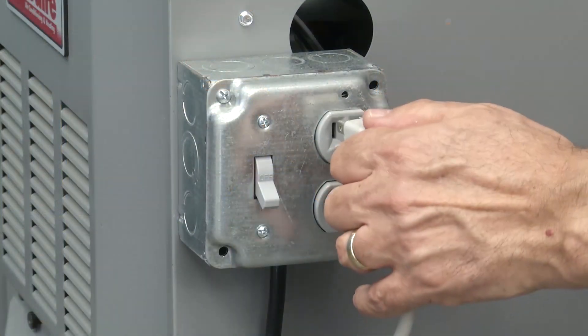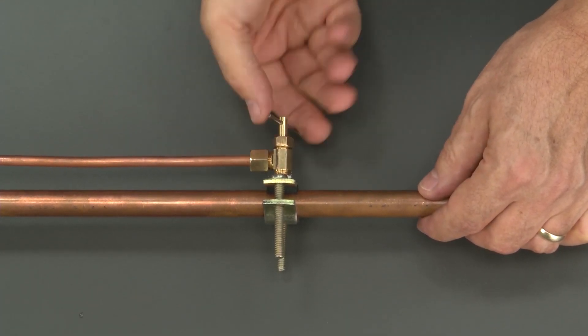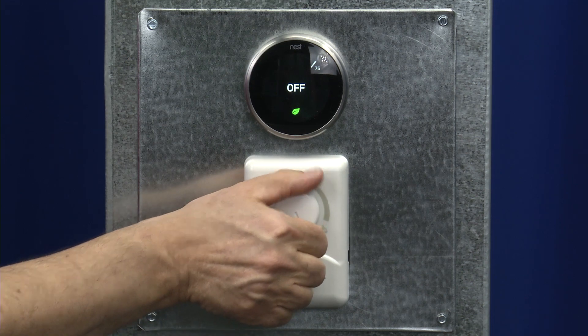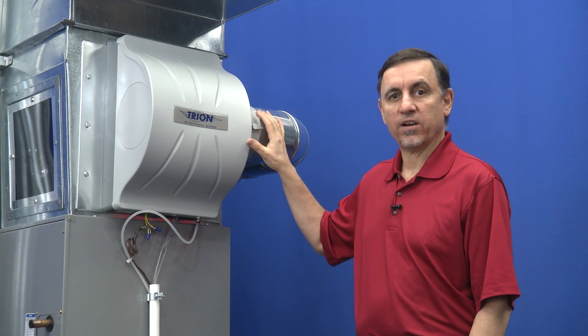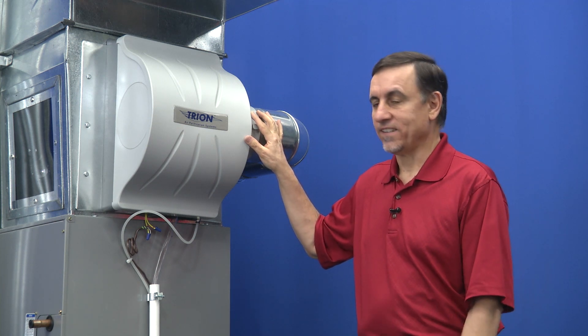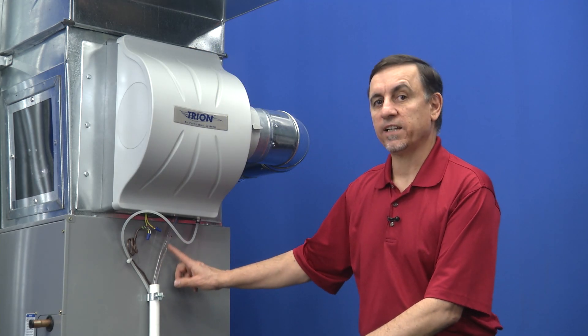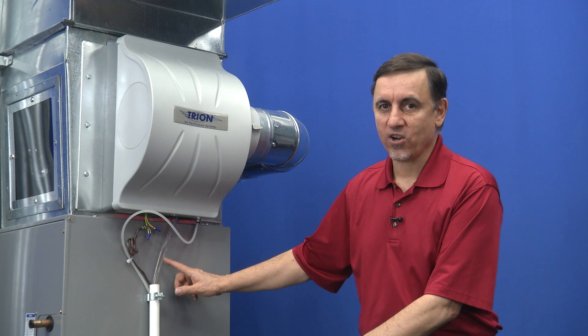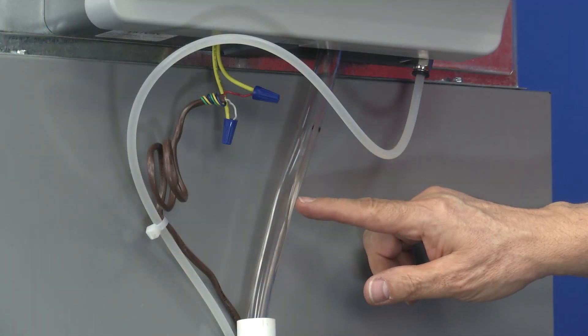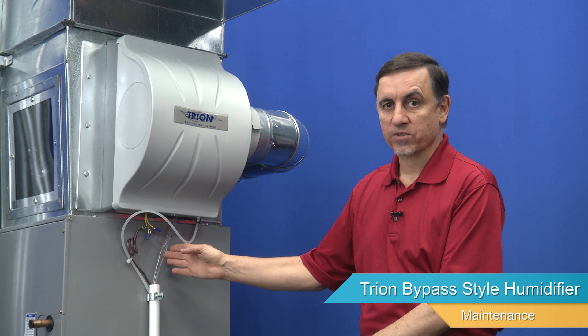Now let's test it. Now that everything else is done, you can turn the water back on. Locate your saddle valve and turn it counterclockwise. Now that we have the water and electricity turned back on and the humidistat spun up to the highest setting possible and the furnace running, we're able to test it. When this thing is running, there'll be water trickling down the drain. If there's water flying out like a fire hose, that's not normal — that's a problem. Right now the thing is running and water is trickling down the drain, so it is working. Now all we have to do is spin the humidistat down and make sure the solenoid valve closes and the water stops running, and we're done testing.